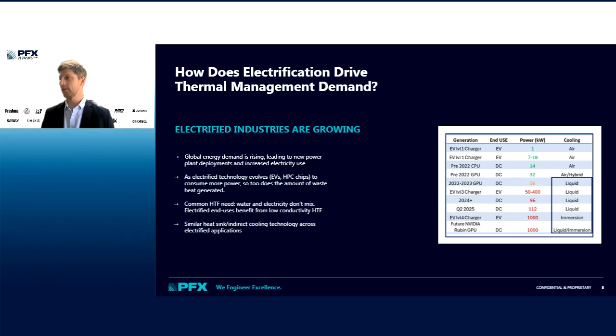In this table on the right, just 5 or 6 years ago on the data center side, an IT rack might have consumed 5 to 10 kilowatts per rack. Today, in the last 3 years, we've moved to over 100 kilowatts per rack. The latest chips from NVIDIA, which dominate the market share of GPUs, require liquid cooling - it's not just recommended, the chips cannot be operated without liquid cooling.